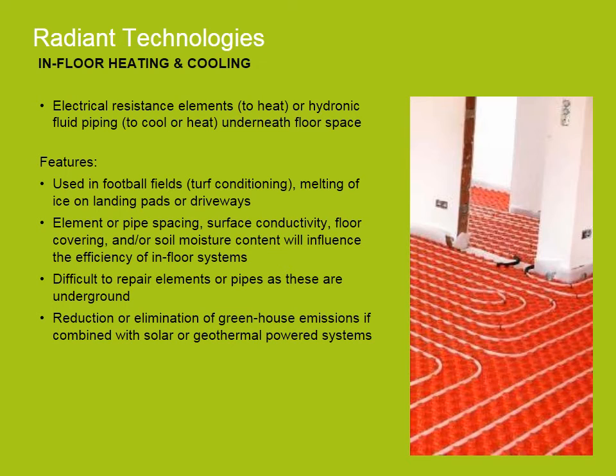In-floor systems can be extremely effective over large open areas where ducted air conditioning may not be feasible, such as areas with higher ceilings, in particular when coupled with solar or geothermal power. The key drawback of this system, though, is access for maintenance and installation, of which there is practically none once a floor has been laid.